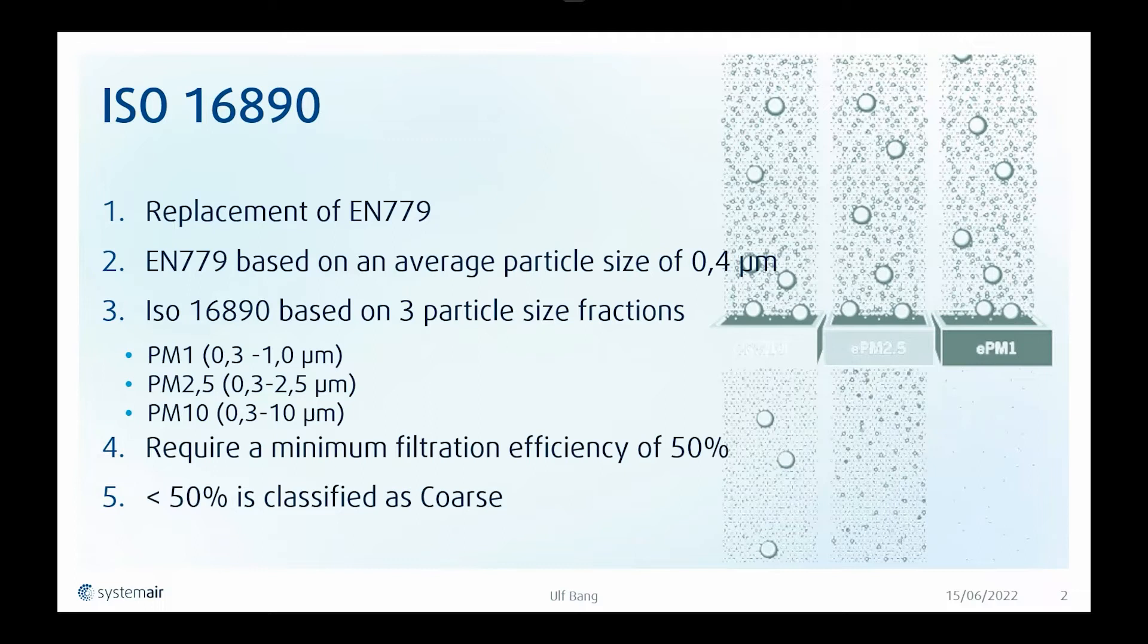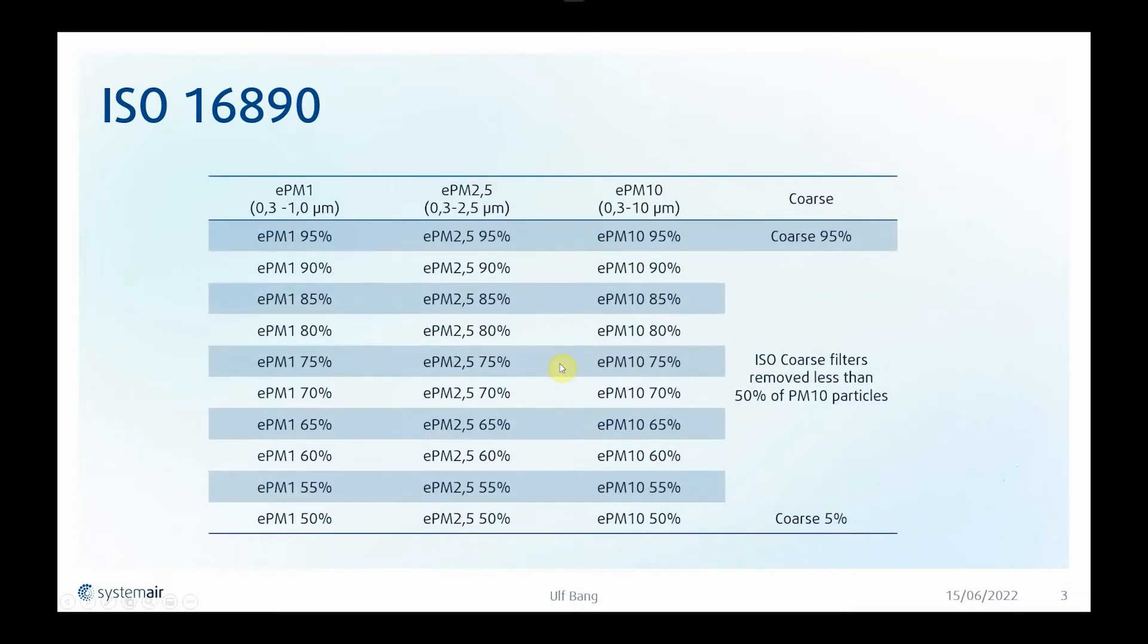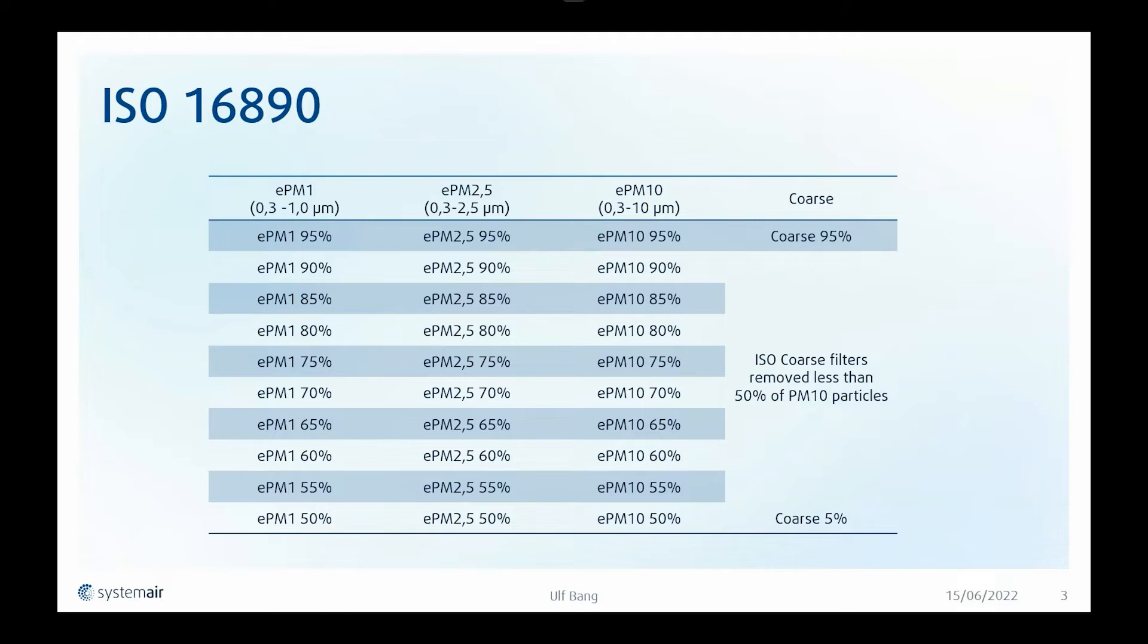So we end up with 30 filter classes divided over the three particle sizes PM 1, PM 2.5, and PM 10 in steps of 5% in efficiency. And then we of course have coarse filters.